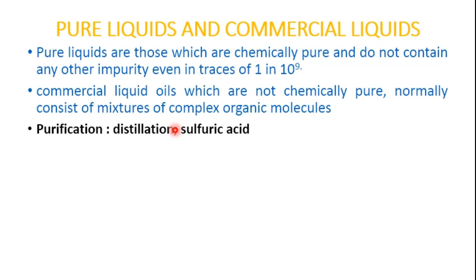Some purification can be done using distillation and sulfuric acid. The main impurities in liquid dielectrics are dust, moisture content, dissolved gases, and ionic impurities. Different methods used for purification include filtration, centrifuging, degassing and distillation, and chemical treatment. Water is removed by using drying agents, and sometimes sulfuric acid is used to remove wax and residues, followed by washing with caustic soda and distilled water.